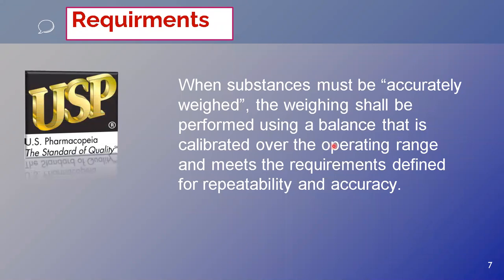Now, what is the requirement? When a substance must be accurately weighed, the weighing shall be performed using a balance that is calibrated over the operating range and meets the requirements defined for repeatability and accuracy. Whenever we are told to weigh accurately, we must weigh on a balance where the weight taken is within that balance's operating range, which is defined on the basis of two parameters: repeatability and accuracy.